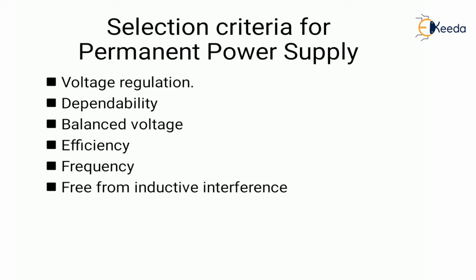So first is voltage regulation. A voltage variation has a larger effect upon the operation of power machineries and the lights. So the voltage fluctuations should be less. If the fluctuations in voltage are sudden, then there may be unnecessary tripping of the circuit breaker and consequently interruption to the service. So the voltage variation has to be within limits.